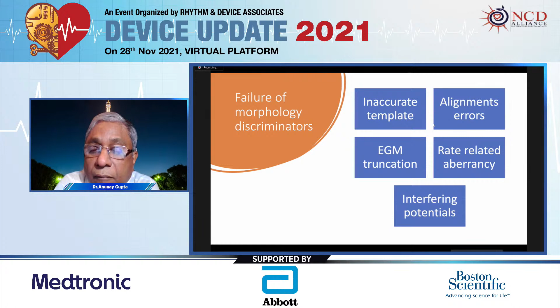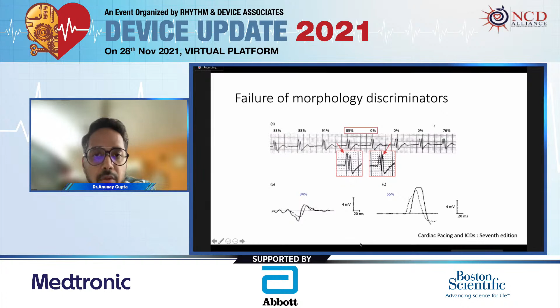One important condition where the morphology discriminator will fail is when the patient develops rate-related aberrancy, because in that case the template will be exclusively different from the sinus template, and the patient will receive an inappropriate shock. And as I've discussed, interfering potentials can also lead to a problem in the matching. A few examples here: this is a sinus beat, which is being matched at 88, 91%. But if we don't align the time marker correctly, suddenly it becomes 0%, while the beats on the EGMs are absolutely similar. Similarly, some interfering potential can lead to a poor matching of 34%. And if the EGM is truncated, it will not match properly and will be misclassified as a ventricular event.